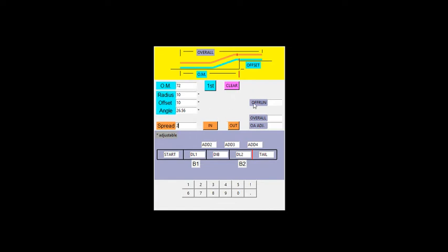Okay, so first thing I want to point out is this little red line here, and this corresponds to this little red line on your first conduit. And you can see here also for this next conduit it shifted, but it shifts by the parallel adjust, and that's basically the only thing that happens when you do an offset and parallel. It just shifts the offset triangle. Your overall length will not change.